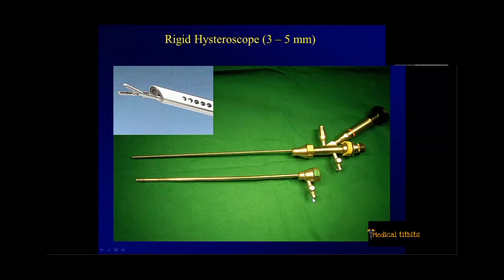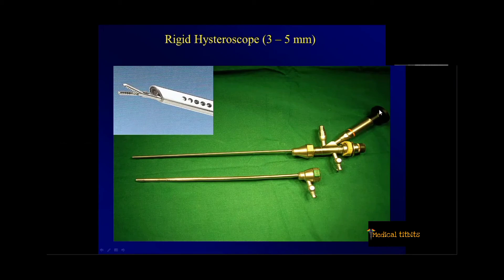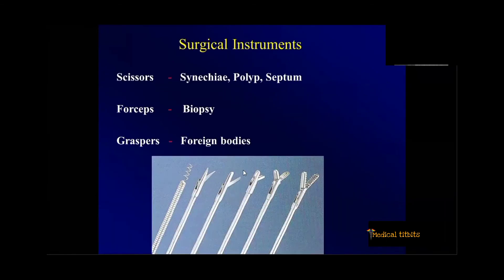There is a water inlet and water outlet. We can use instruments that are straight, so we can have continuous flow, and all instruments can be put through the channel. Another model has the scope straight and the instrument channel at a slight angle — the advantage is instruments can come out straight, but the problem is it is an integrated system so the vision is not as good. All energy sources we can use include monopolar with the integrated system, or other instruments like graspers and scissors.